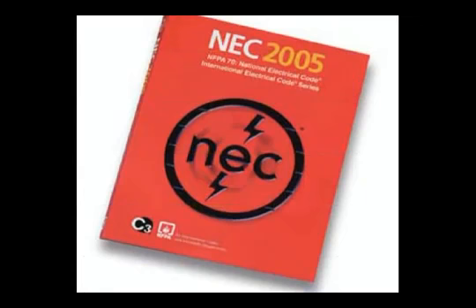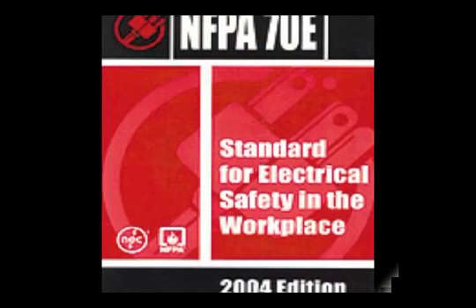Every state in the U.S. uses the National Fire Protection Association's publication known as the NEC, or the National Electrical Code. This code is technically known as NFPA 70. At the request of OSHA, the NFPA published a new standard for electrical safety in the workplace known as NFPA 70E. The NFPA 70E Section 130.3 says: a flash analysis shall be done in order to protect personnel from the possibility of being injured by an arc flash. The analysis shall determine the flash protection boundary and the personal protective equipment that people within the flash protection boundary shall use.